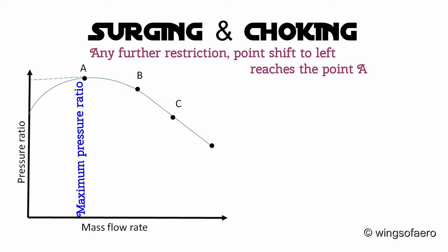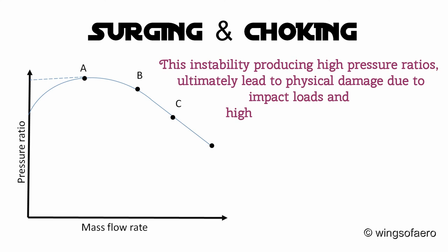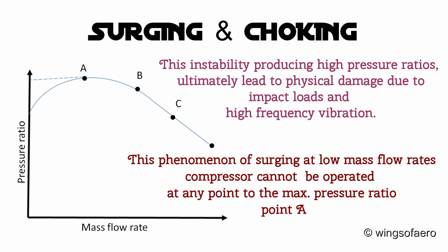If flow is still reduced from point A, the compressor cannot increase the pressure ratio any further and the pressure ratio starts reducing. This reduction in downstream pressure causes the compressor to again start delivering fluid and the operating point shifts back to point C. The pressure then starts increasing again and the operating point moves left once more. If downstream conditions are unchanged, the flow breaks again at point A and this cycle repeats at high frequency — this phenomenon is called surging or pumping.